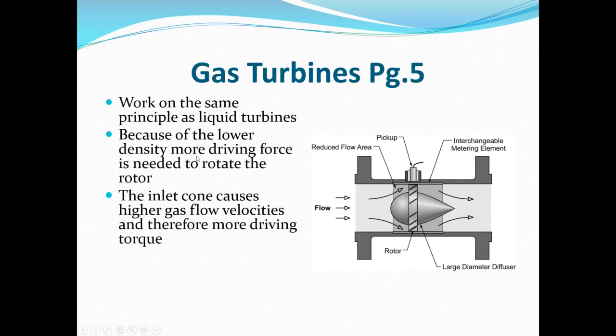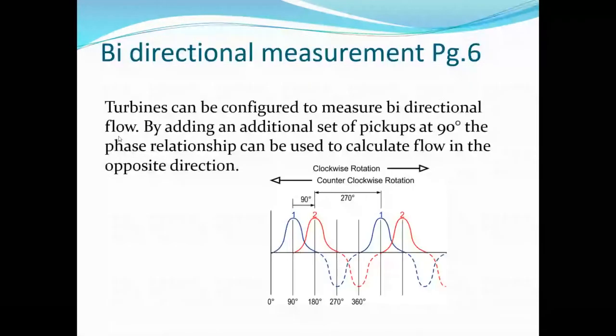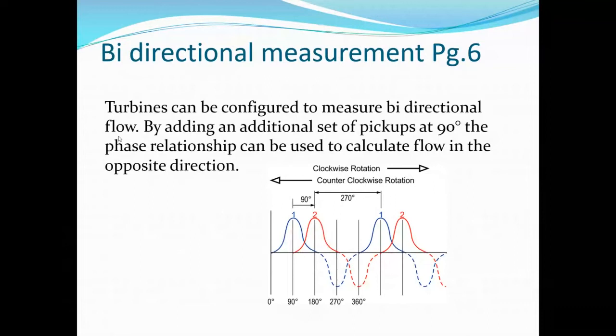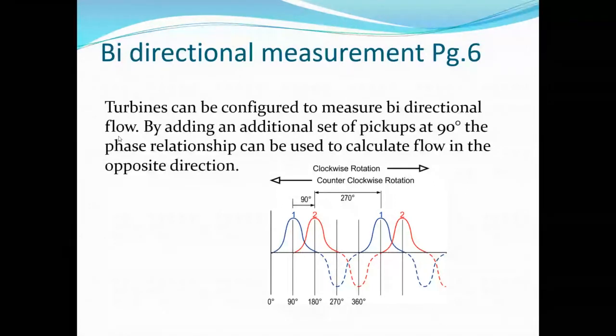Some turbine meters can be configured to measure bidirectional flow. The way they do this is by adding an additional set of pickups at 90 degrees. The phase relationship between the two pickups is used to calculate flow in the opposite direction — if one is in phase ahead or behind the other, the direction of rotation can be determined. So these are bidirectional devices.